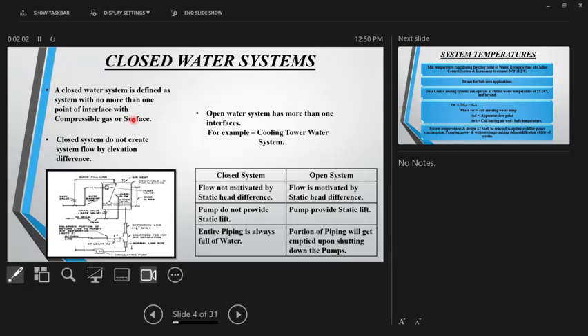If you talk about chill water systems 20, 30, 40 years back, they used to have an open expansion tank on the terrace, correct? It used to be a small 1,000 liter or 2,000 liter tank, mainly plastic. So is that also a closed chill water system? Yes, because it has only one point of interface with the surface, which is the atmosphere. There is no other part in the system which is open to the atmosphere. So those chill water systems with an open expansion tank on the terrace are also called closed water systems. Nowadays, obviously, we have these closed expansion tanks. There also, there is only one interface, between the bladder and the inert gas, correct? There are no two interfaces.